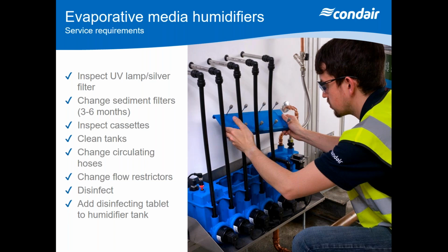When you're going to be disinfecting, you're going to be putting in chlorine, which is a requirement by HSE. We're putting 50 parts per million of chlorine into the tank and trying to circulate that around the system. Depending on the size, it might be 1 or 2 hours. And then what we're going to do is dilute that chlorine and then use a neutralizer to get rid of the chlorine in the system.